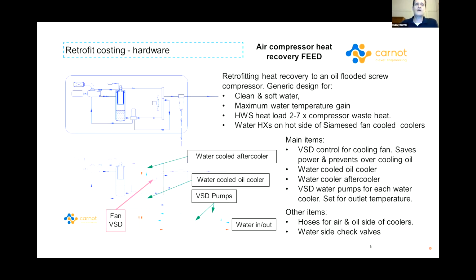So the main thing you're adding is a VSD for the cooling fan. If you don't turn the cooling fan off, it will overcool the oil and still reject heat. It's also a direct power saving as well. If you can turn the fan off with a VSD, that's great. The VSD is controlled by the temperature of the oil coming out of the air end. If it gets too hot, the fan starts cooling. Easy.